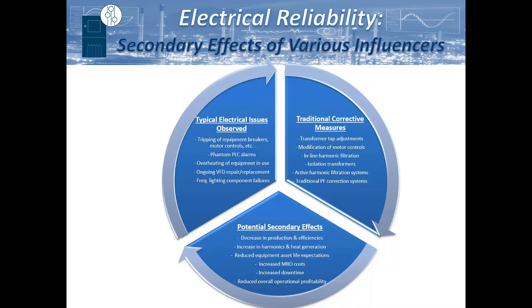Also, overheating of equipment, whether that be from an imbalance or elevated current draws, things of that nature, and how that impacts equipment asset life expectations, and even some small things that may not oftentimes be attributed to power quality, but can have a strong correlation. Quite frequently we'll have clients call saying that they've had a brand new LED installation and they have frequent component failures, thinking that it's a manufacturing defect, when in actuality oftentimes it's a result of the dynamic nature of the network, whether that be from voltage variations or harmonics, and the impact on the components within those networks.